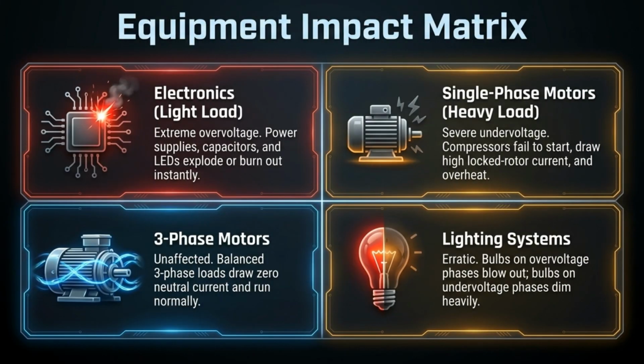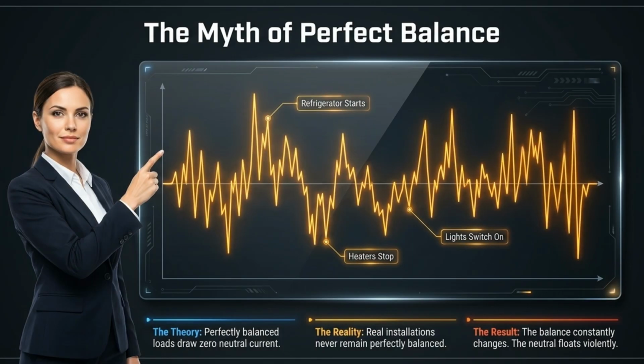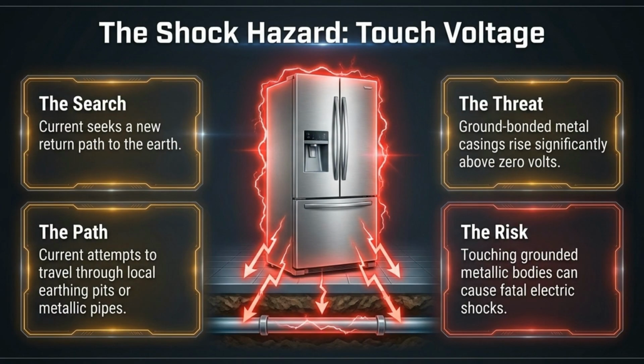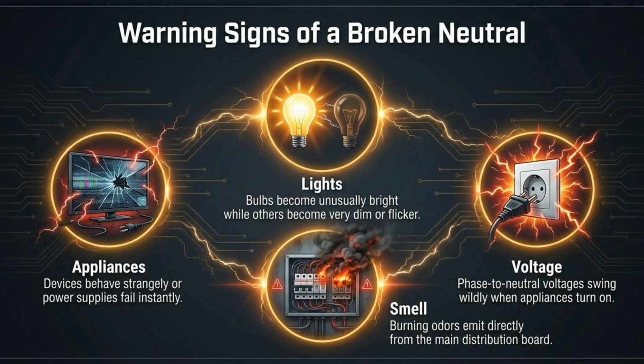The impact on equipment is severe. Electronics can explode from overvoltage, motors can overheat from undervoltage, and lighting systems will dim or blow out entirely. The myth of perfect balance doesn't hold up in the real world. As appliances turn on and off, the neutral point constantly shifts, making the system inherently unstable. Perhaps the greatest risk is the shock hazard. With a floating neutral, metal casings of appliances can rise above 0 volts, turning them into a lethal touch risk. Warning signs include lights changing brightness, appliances behaving erratically, or the smell of burning coming from your distribution board.